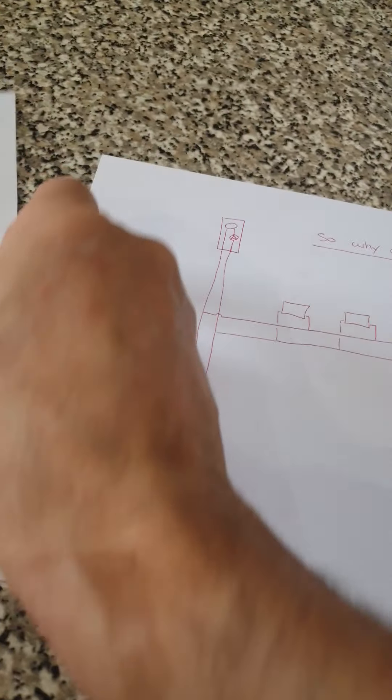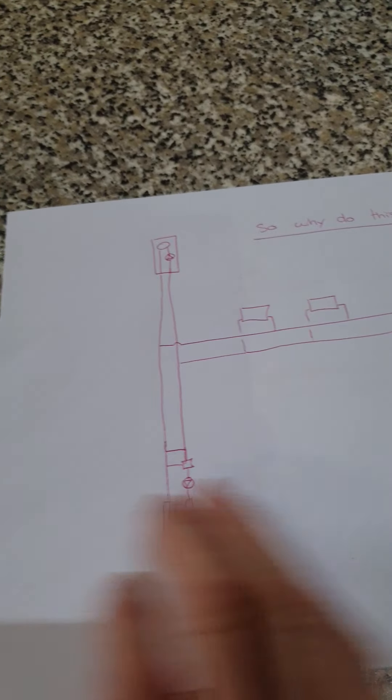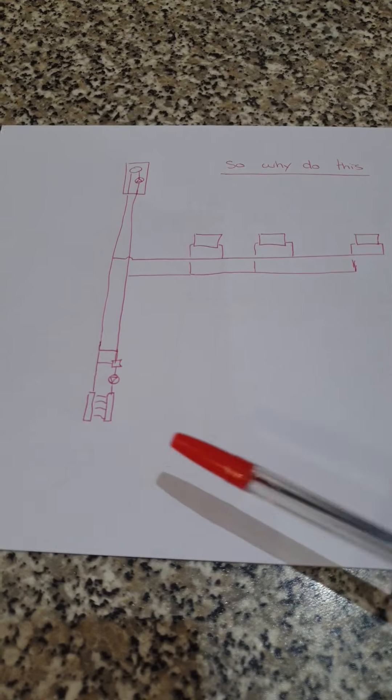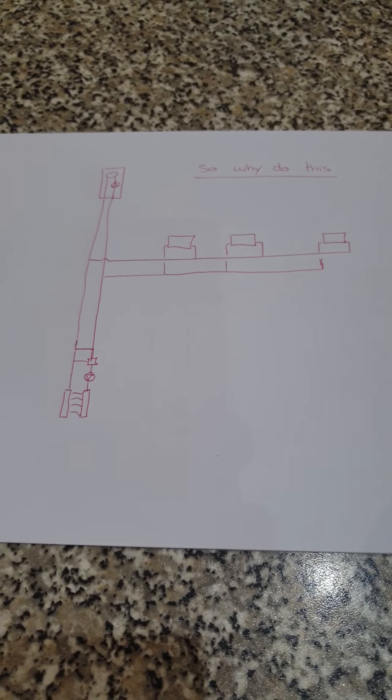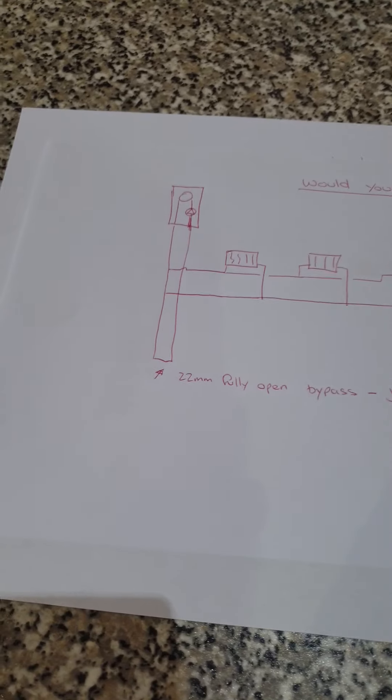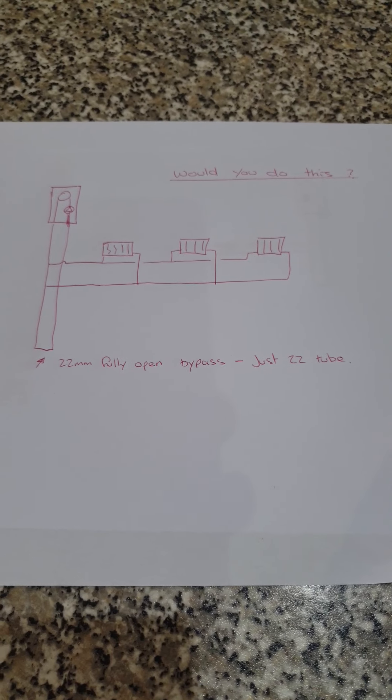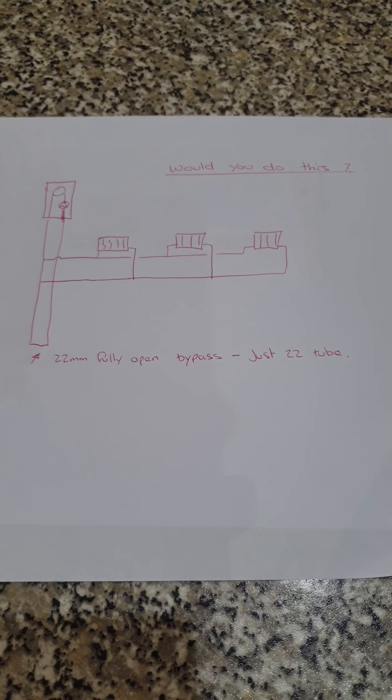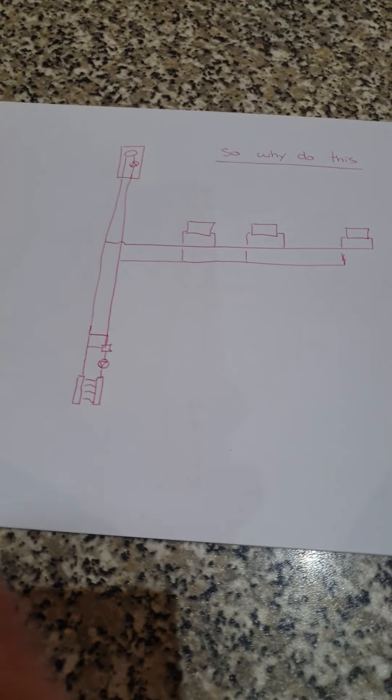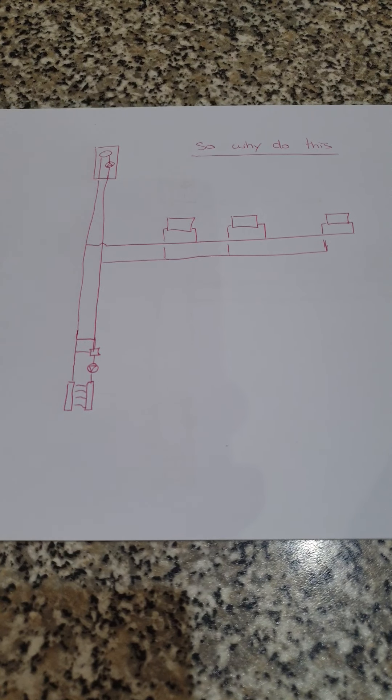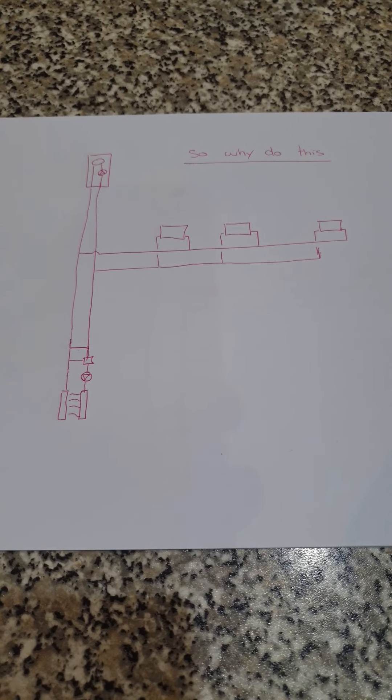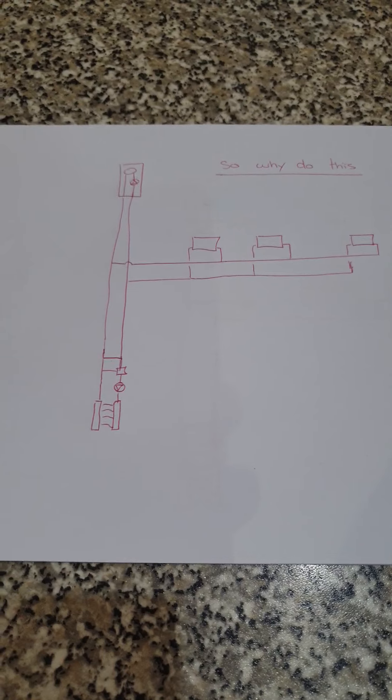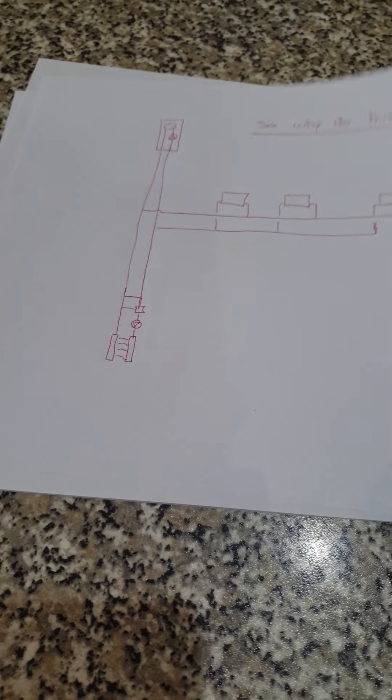They're putting in close coupled tees at the underfloor heating and creating exactly the scenario in my first drawing. Which is so blatantly obviously wrong that I can't believe that people thought that this was correct. This is obviously very, very wrong and should be avoided.